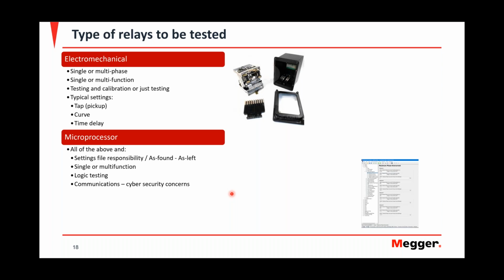Again, single or multifunction, the logic testing. Sometimes testing the actual elements and the protection functions becomes the easier thing, but when you talk about the logic and all the different combinations or permutations of logics that you could have, that becomes a really bigger challenge than the actual testing. And that's something you have to keep in mind when you talk to your boss and say, "Hey, I'm being sent to test the relay, but I'm not testing just the elements." That's the easy part. It's the logic and how it encompasses the whole application that could become a bit tougher to test, and something that will require more time.